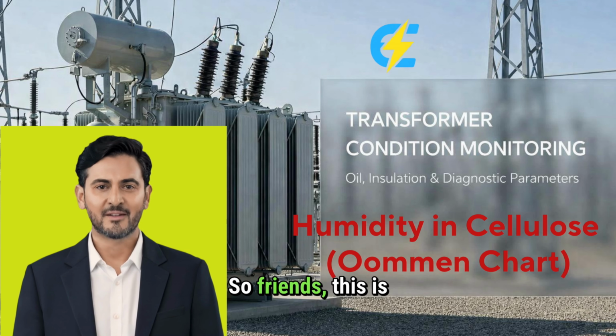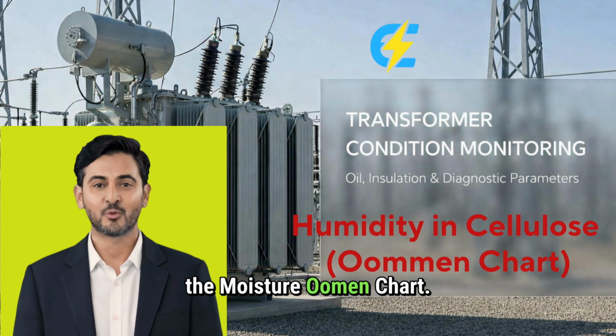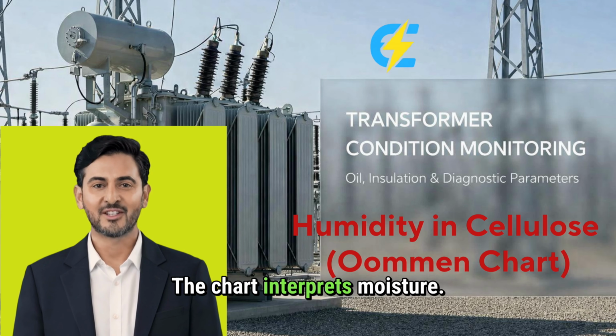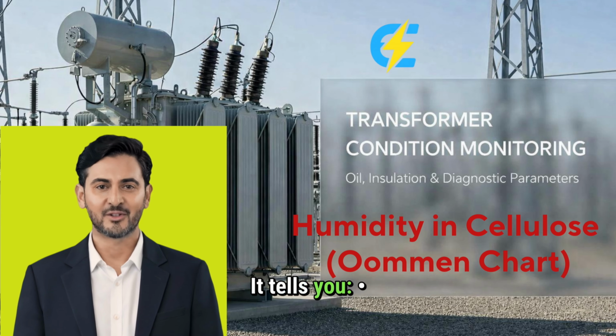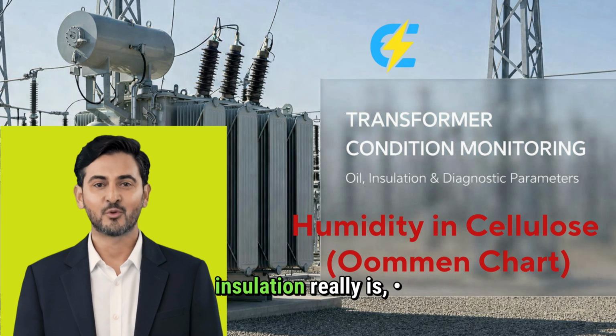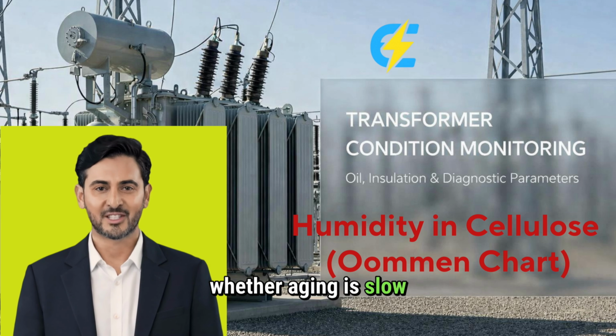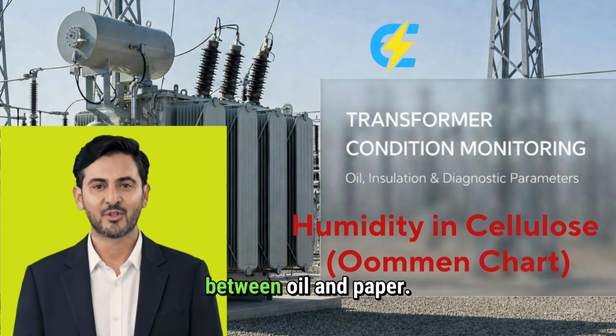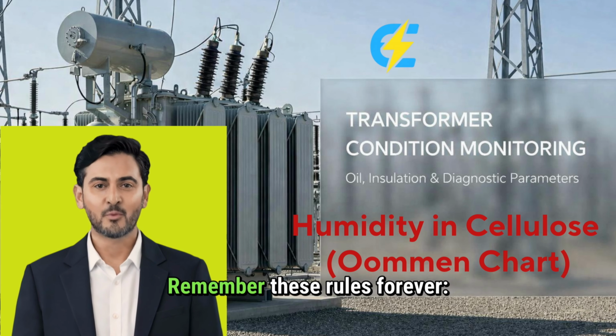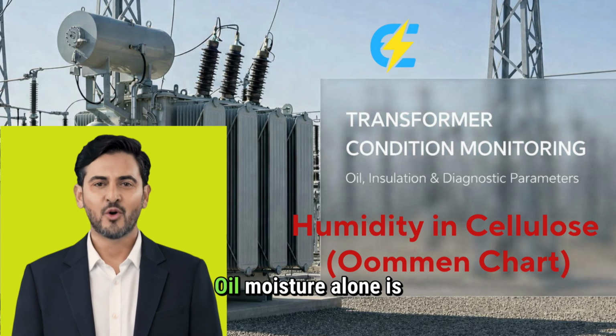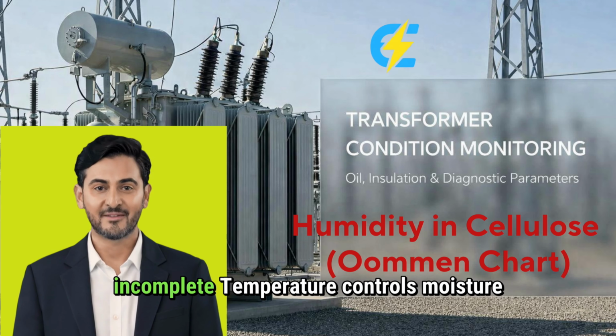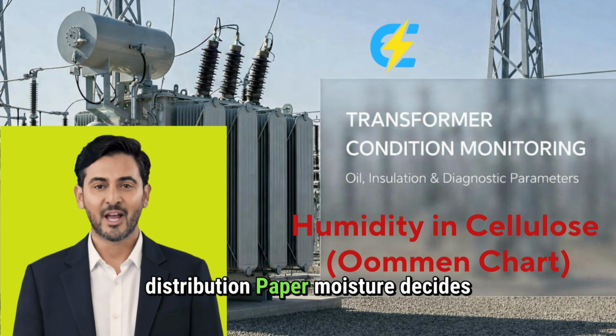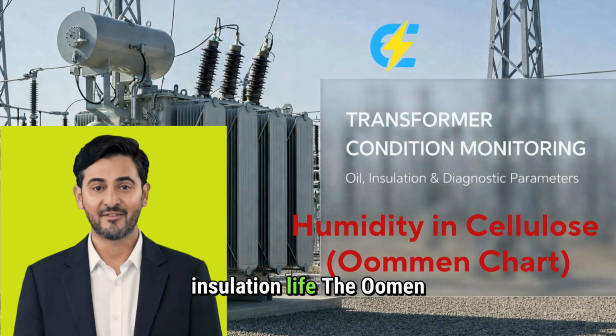So friends, this is the real meaning of the moisture Oommen chart. The chart does not measure moisture. The chart interprets moisture. It tells you how wet the paper insulation really is, whether aging is slow or accelerating, and how temperature shifts moisture between oil and paper. Remember these rules forever. Oil moisture alone is incomplete. Temperature controls moisture distribution. Paper moisture decides insulation life.